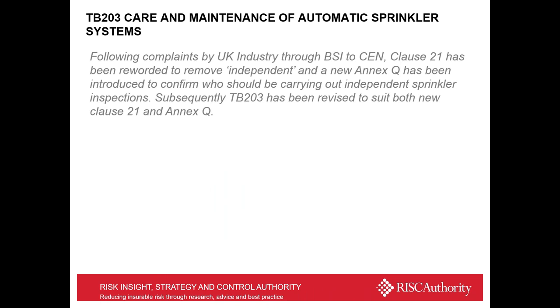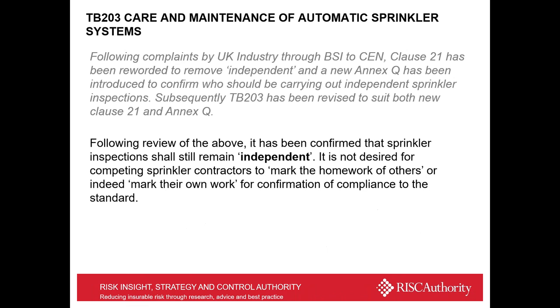And following complaints by the UK industry through BSI to CEN, and this is the reason for the new BS EN 12845:2015 plus Amendment 1 2019, confirmation of who should be carrying out independent sprinkler inspections. Now, following a review with the insurers and RISCAuthority, it's been confirmed that inspections shall still remain independent, and it is not desired for competing sprinkler contractors to mark the homework of others or indeed mark their own homework for confirmation or compliance to the standard.